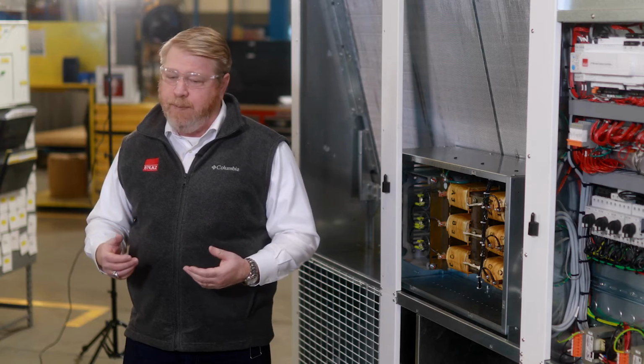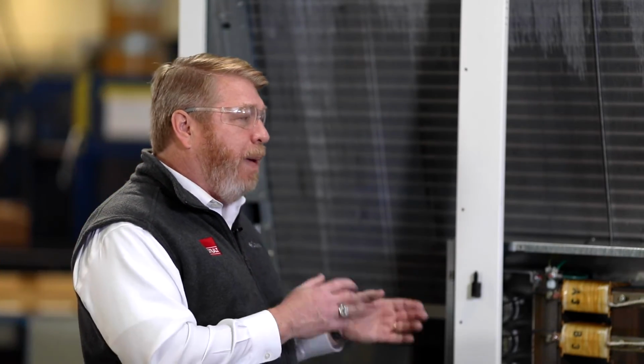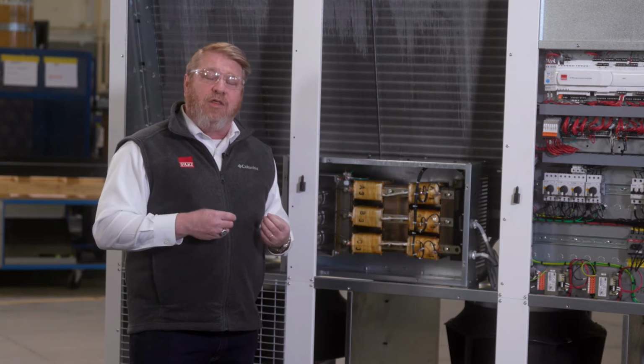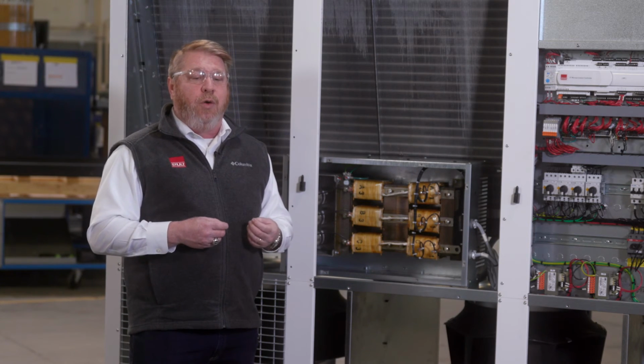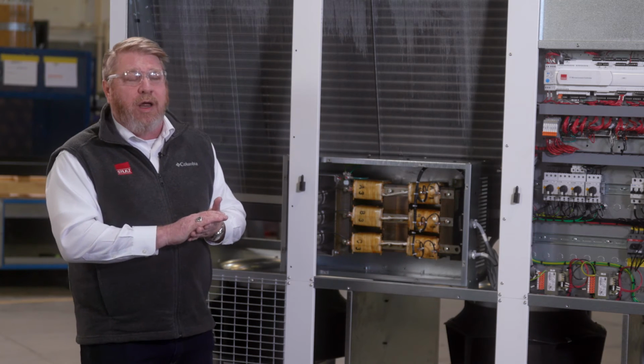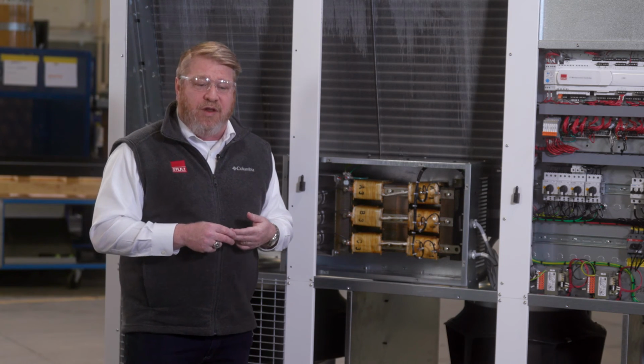Now, the way we approach this is we use either an active or a passive harmonic filter. What this does is filter out the signal such that we get much closer to the original sine wave signal that was coming into the unit. By filtering these harmonics, we're able to lower our peak current, maintain temperatures within the device, lower the electromagnetic emissions of the unit, and also protect the core of the motor.